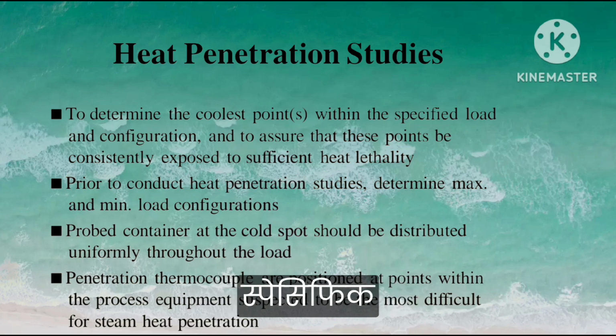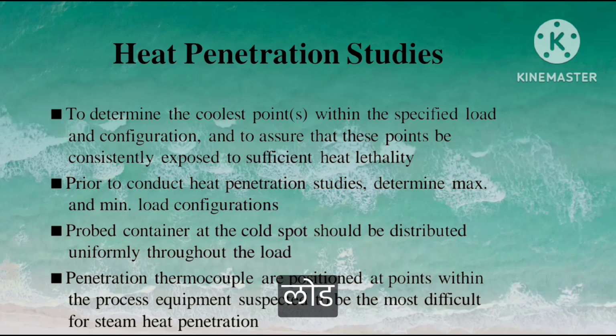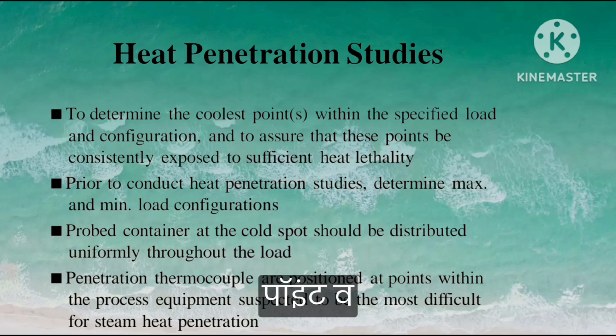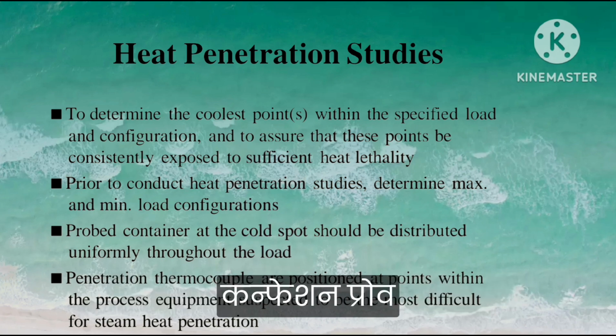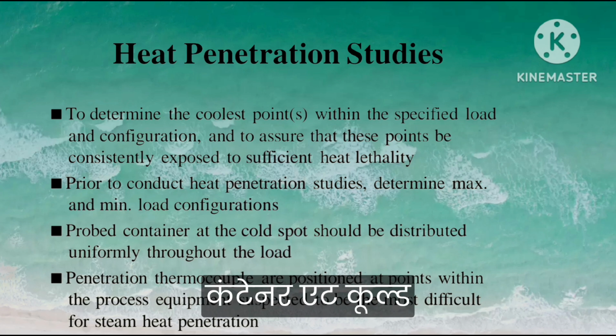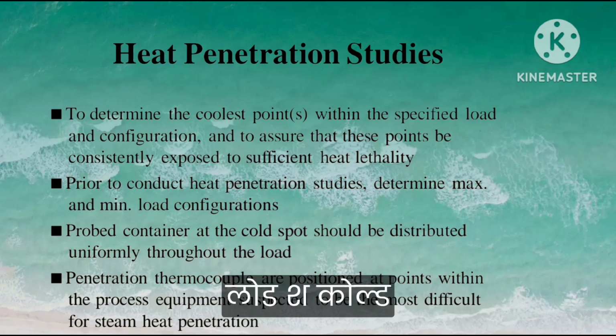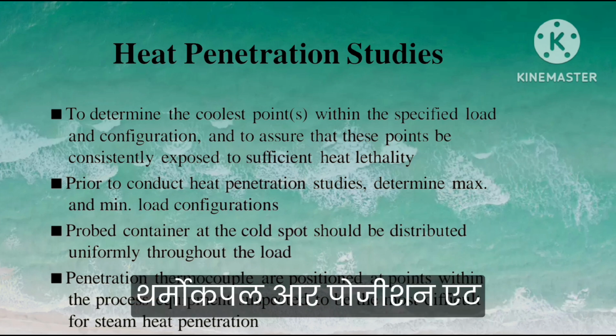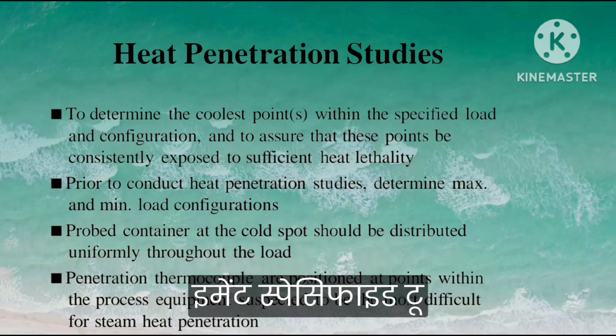Heat penetration study क्या होती है? To determine the coolest point within the specific load configuration and to assure that these points are exposed to sufficient heat lethality. Prior to conducting heat penetration studies, determine maximum and minimum load configuration. Probe containers at the cold spots should be distributed uniformly throughout the load. Penetration thermocouples are positioned at points within the process equipment specified to be most difficult to steam heat penetration.